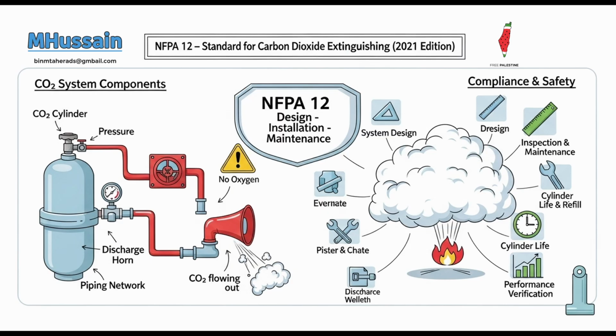Probably not. The warning signs themselves are incredibly detailed, far beyond a generic caution fire system notice. NFPA 12 mandates a comprehensive signage strategy. Signage strategy. Sounds serious. It is. Requiring conspicuous signs in every protected space, at every entrance to protected spaces, in nearby spaces where CO2 could migrate and create a hazard, outside CO2 storage rooms, and at all manual operation points. Signs everywhere. These signs must conform to ANSI Z535.2 in terms of format, color, lettering, and symbols, ensuring they are universally understandable. They typically use a 3-panel format with very specific wording.